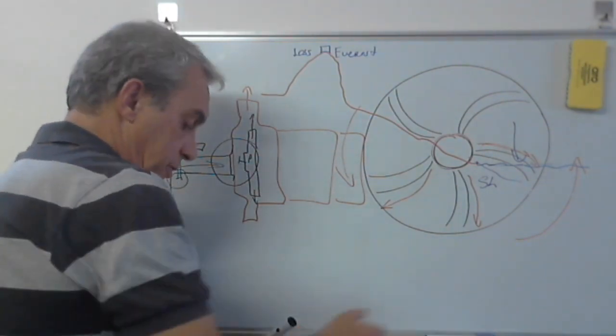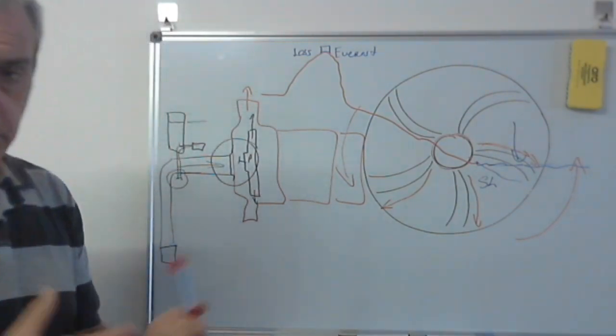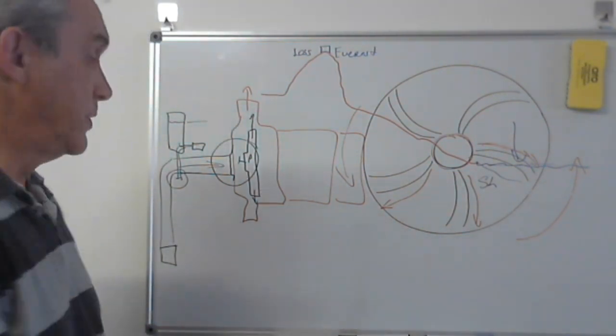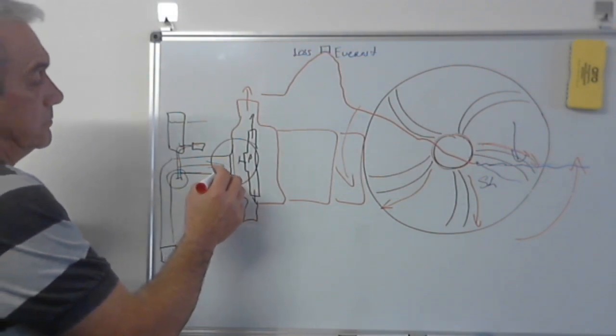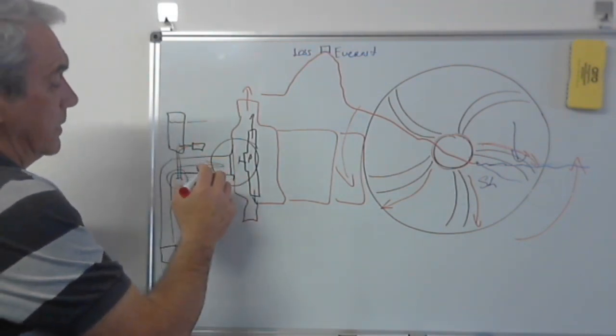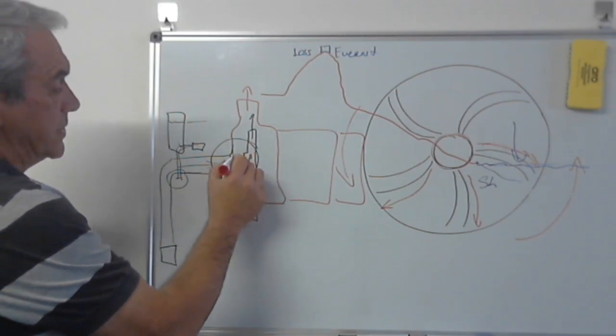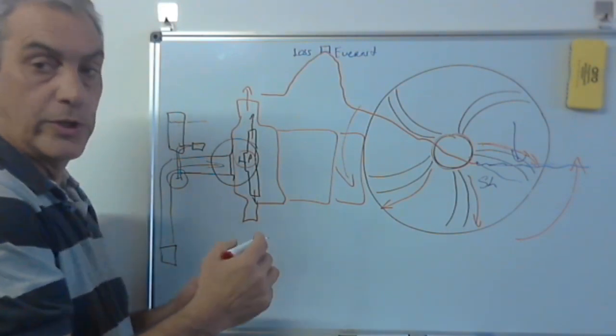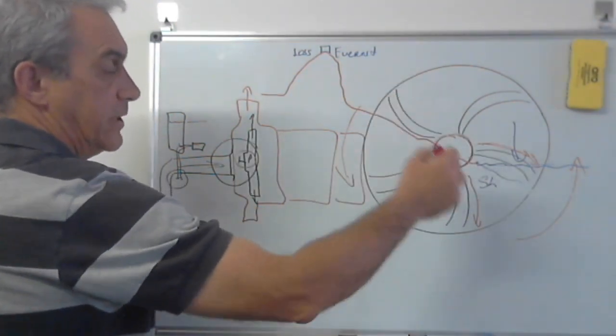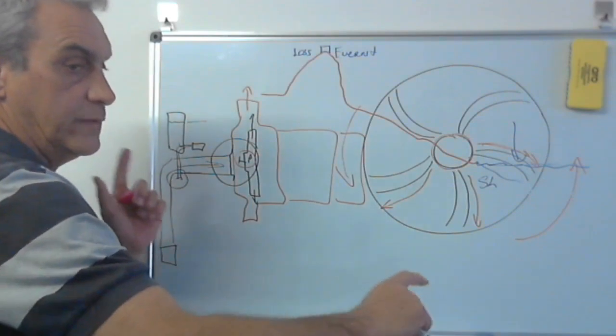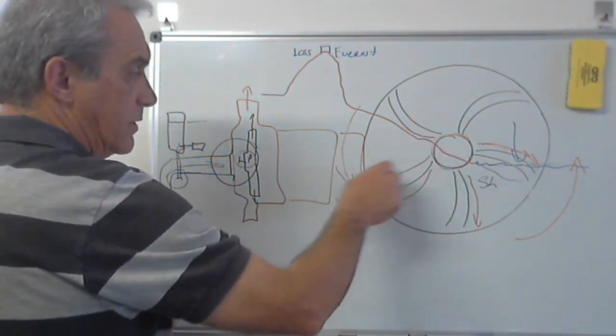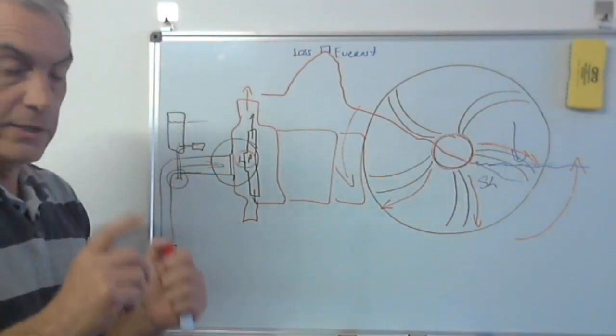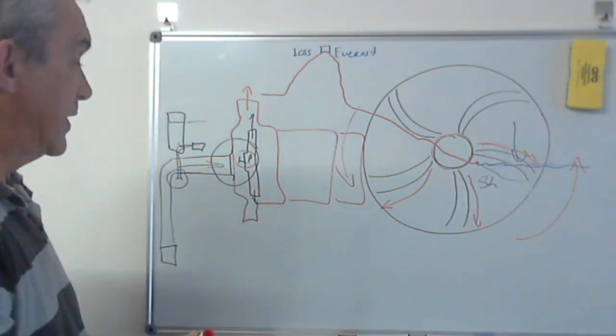The reason I'm telling you all this, besides the fact that you now know how a pump works, and why a pump works, and why a vacuum cleaner works: without this low pressure zone creation, water would not move. It cannot. And the centrifugal force that is being created by spinning of this impeller is what actually moves the water away. That dispersal of water creates the low pressure zone in the eye of the impeller, and that's what creates suction.